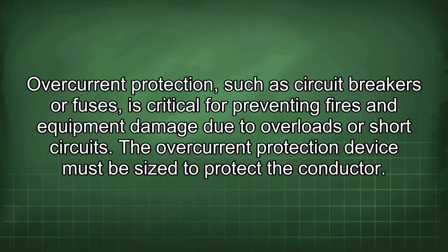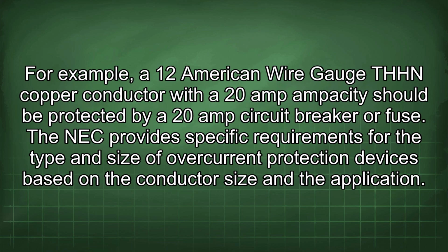Overcurrent protection, such as circuit breakers or fuses, is critical for preventing fires and equipment damage due to overloads or short circuits. The overcurrent protection device must be sized to protect the conductor. For example, a 12 American wire gauge THHN copper conductor with a 20 amp ampacity should be protected by a 20 amp circuit breaker or fuse. The NEC provides specific requirements for the type and size of overcurrent protection devices based on the conductor size and the application.